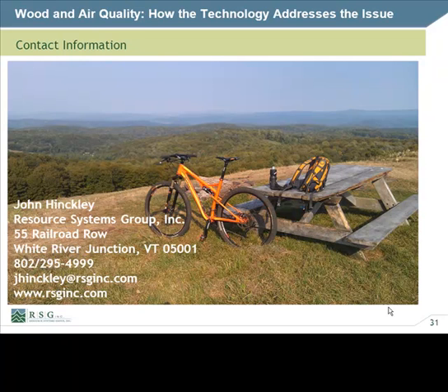Sure, so the gist of the question is about what's going on with a lot of biomass systems. Let's take one that heats a public school. When school lets out, and early in the wee hours of the morning, the boiler will cut on to warm the building up. The building will be calling for heat, and the boiler will rise to the occasion, turn on and rise up to what I call high fire, close to 100% load, full design capacity, making a lot of steam to produce heat for the building. Typically that's when a boiler runs most efficiently.